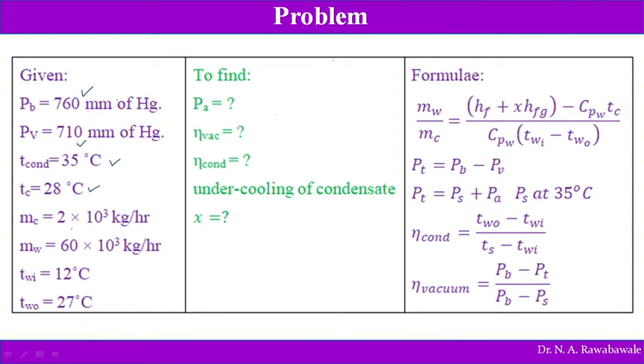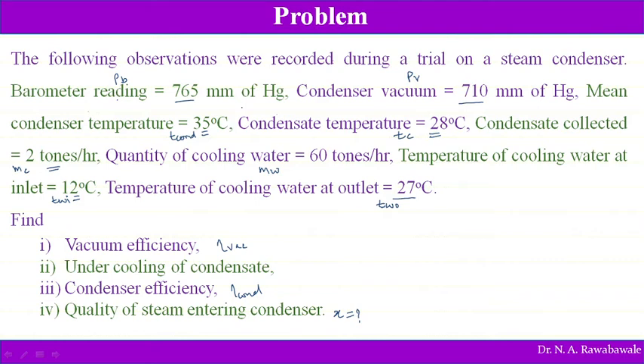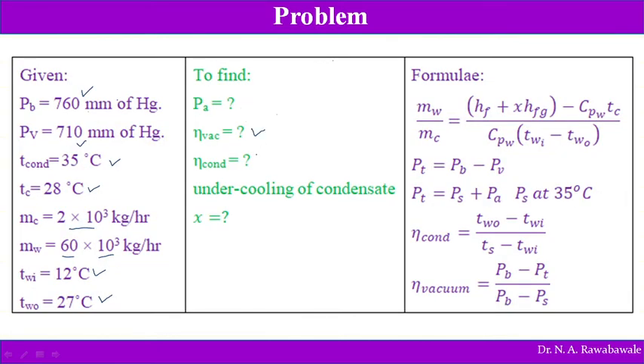We are asked to find vacuum efficiency, under-cooling (sub-cooling), condenser efficiency, and dryness fraction of steam. Under-cooling means the steam condenses at 35°C but the condensate leaves at 28°C — the difference of 7°C is the sub-cooling. We need to calculate condenser efficiency and dryness fraction as in the previous case.